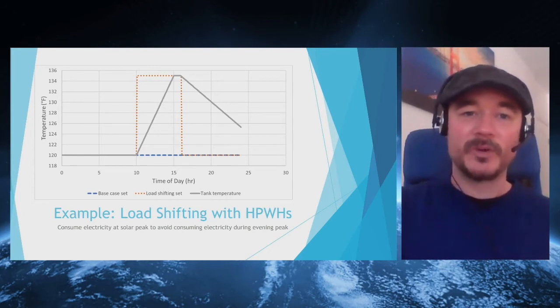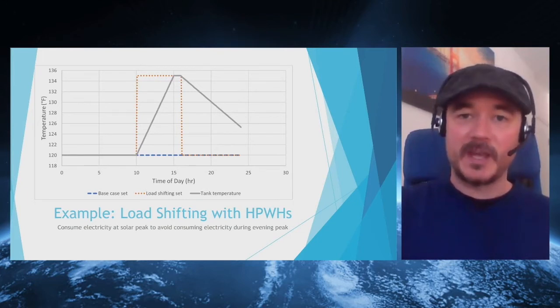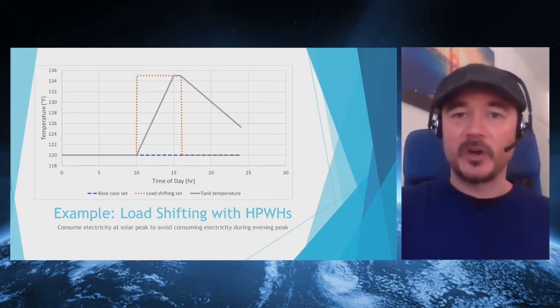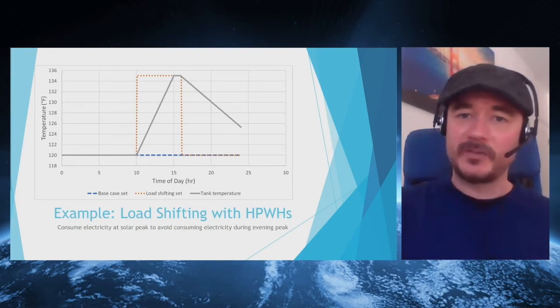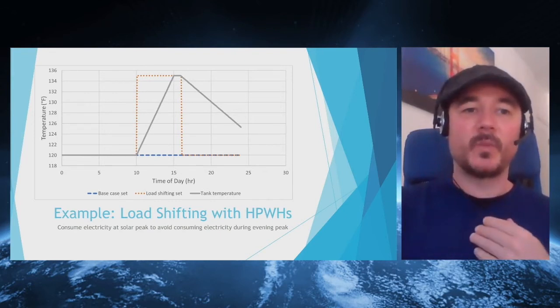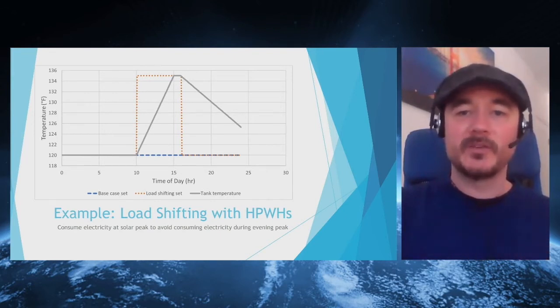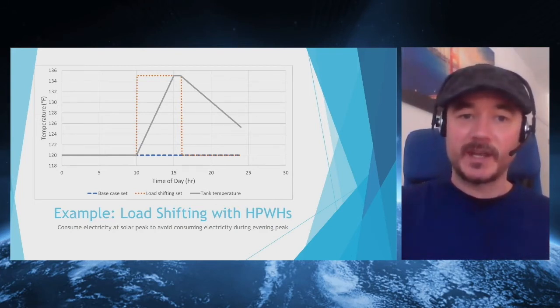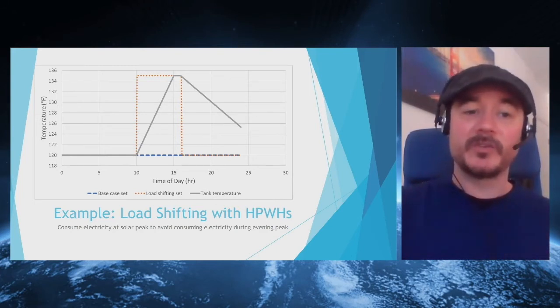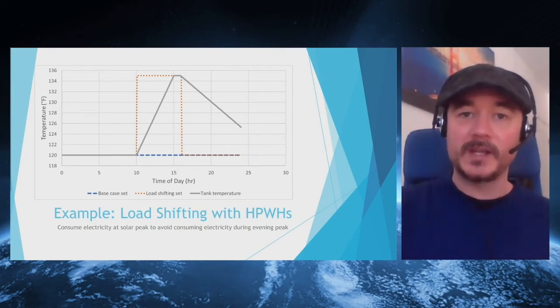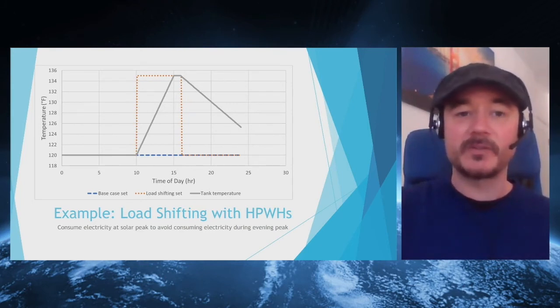But for now, what we're really showing is the control strategy used in load shifting. The blue data represents the base case, where we have a set temperature of 120 degrees, constant throughout the day, and the water heater only does what it needs to keep the water at 120 degrees. In the load shifting case, at 10 a.m. we increase the set temperature from 120 to 135 degrees.